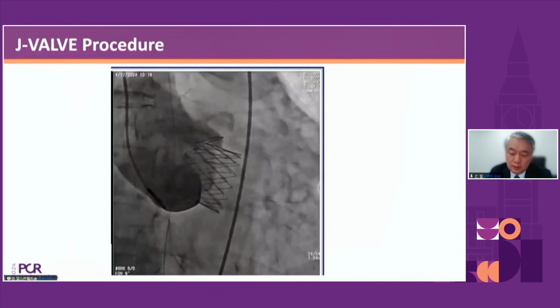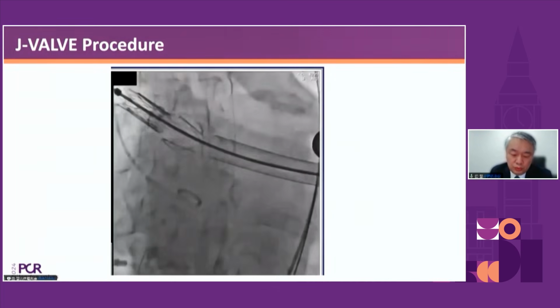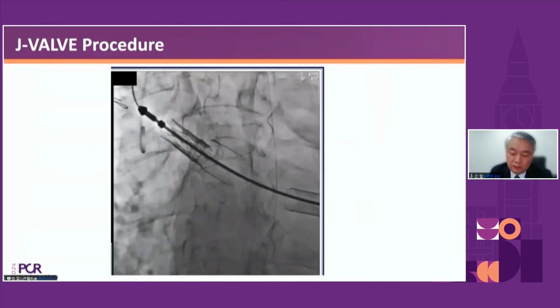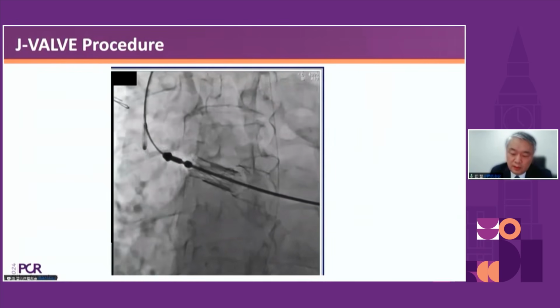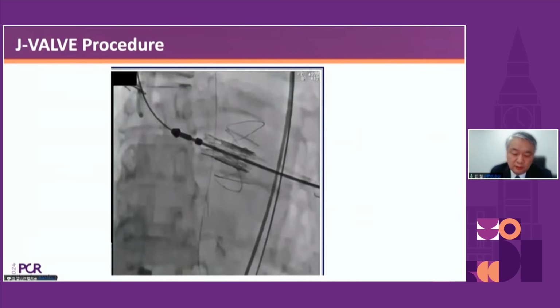The anchor ring springs open. Pull back the delivery system to ensure the anchor rings are locked onto the native aortic sinus. Turn control knob 2 to place the valve at the position of the native aortic valve. Turn control knob 3 to release the valve.